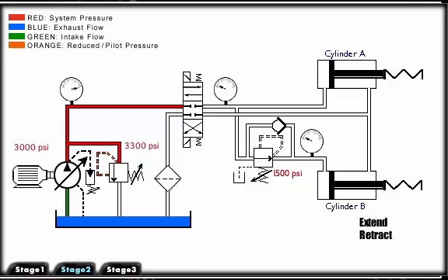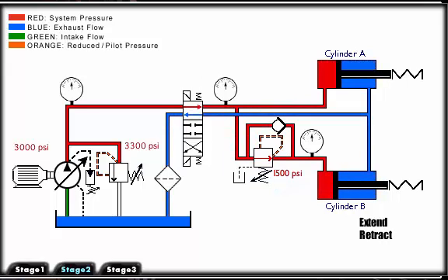The illustrated clamp circuit requires that clamp cylinder B apply a lesser force than clamp cylinder A. A pressure reducing valve placed just before clamp cylinder B will allow flow to go to the cylinder until pressure reaches the setting of the valve.